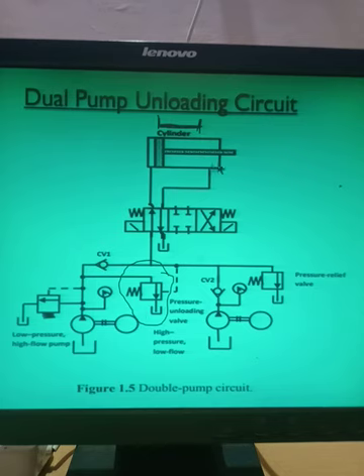From here onwards the pressure will be very high, and as the pressure will be very high you can do the punching operation here. Now what is the use of this circuit? The use of this circuit is that there is a tremendous power saving by using the unloading valve.